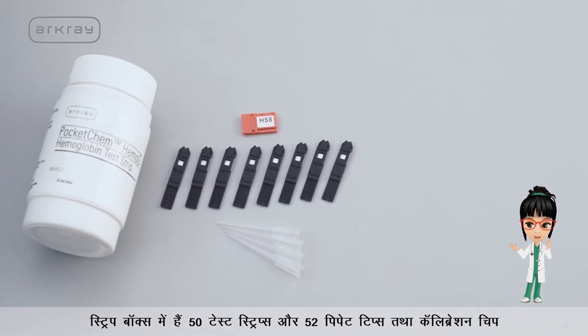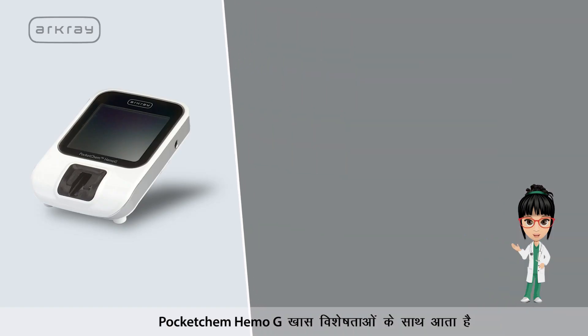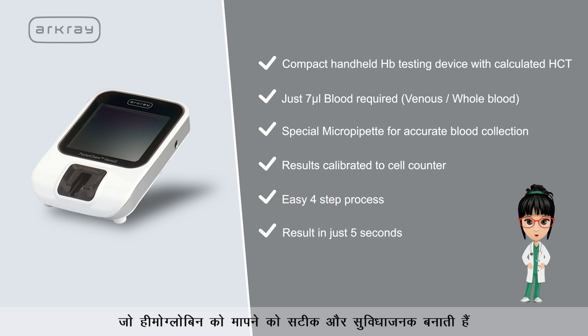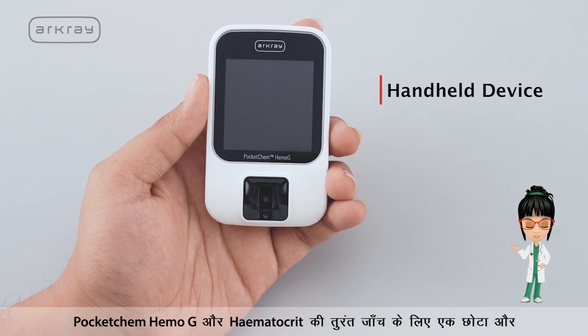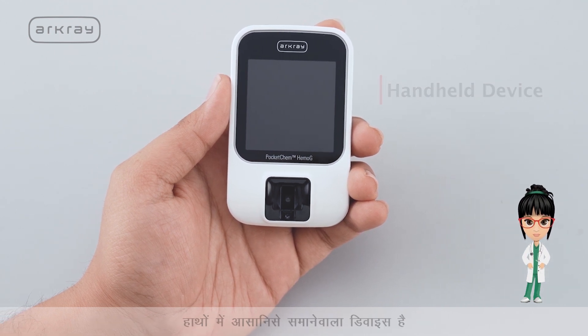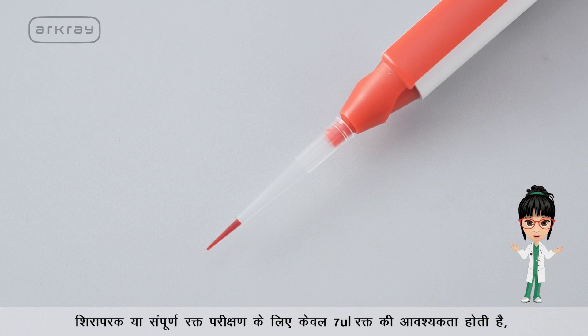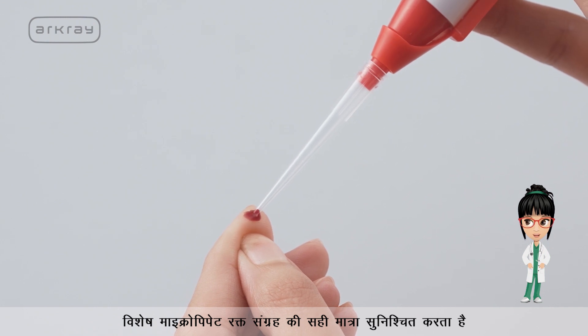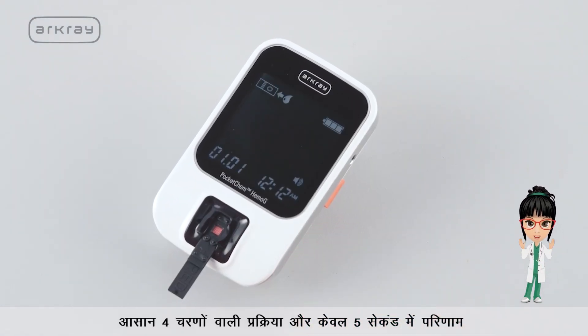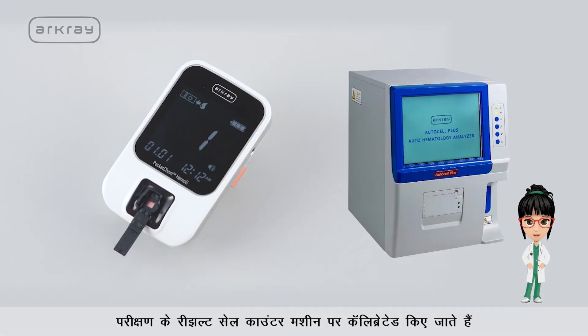The strips box contains 50 test strips with 52 pipette tips and a calibration chip. PocketChem Hemo G comes with features that make measuring hemoglobin accurate and convenient. It is a compact handheld device for checking hemoglobin and hematocrit instantly. Just 7 microlitres of blood is required, whether venous or whole blood. The test results are calibrated to a cell counter.